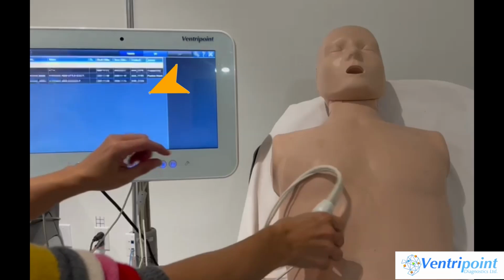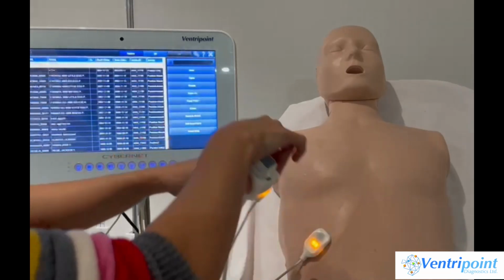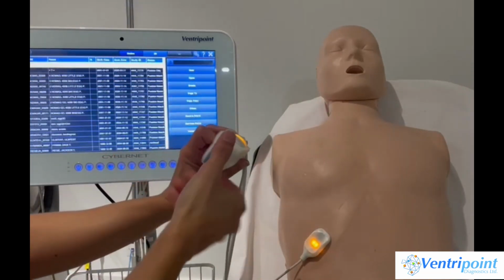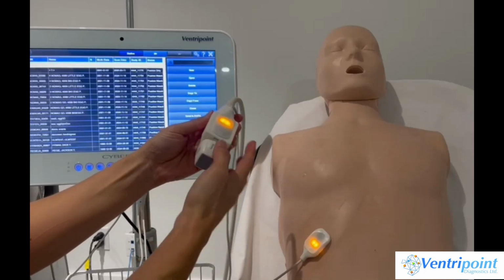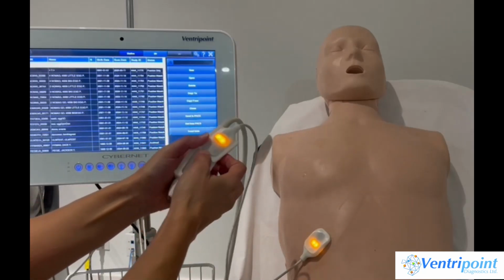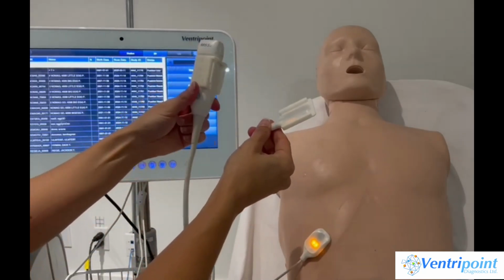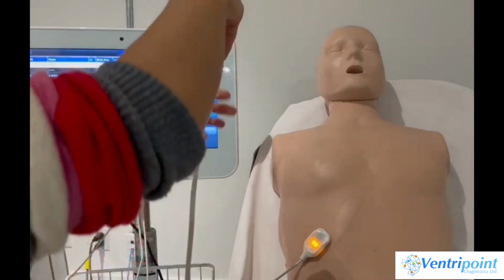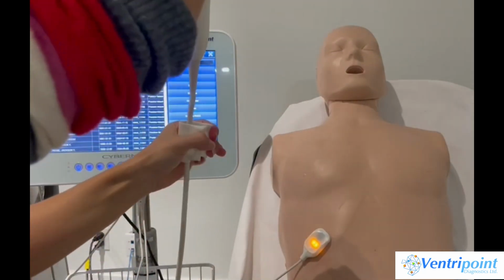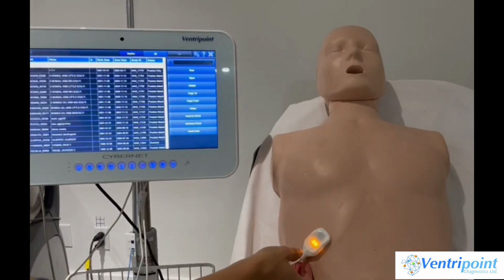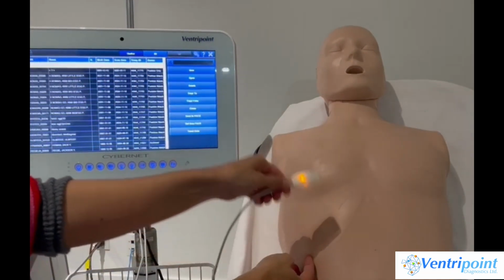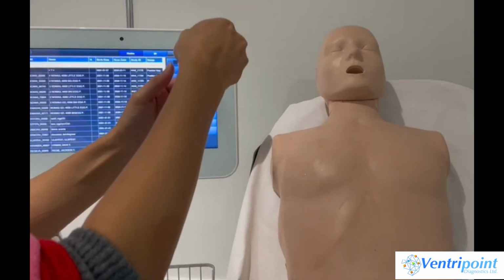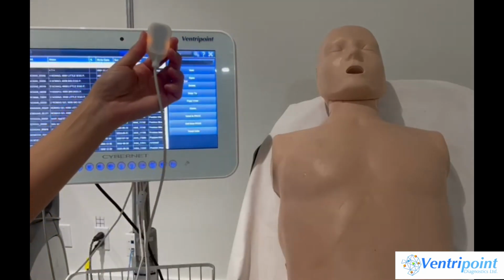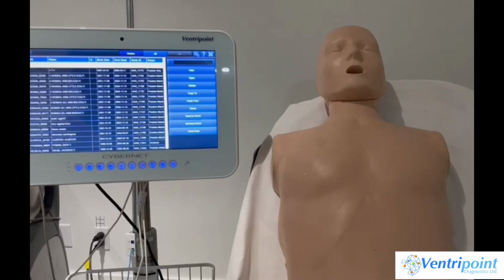Press OK. To remove the probe sensor, push the sensor along the sleeve tracks using your thumb with your fingers gripping the sleeve. To remove the probe sleeve, hold the probe up and pull the sleeve down. The probe lead passes through the split. Now remove the patient sensor, and peel the sticking tape off the sensor surface. Please remember to clean the sensors as per the instructions in the VMS Plus user guide.